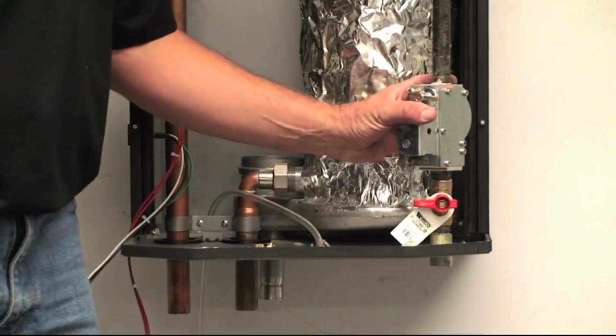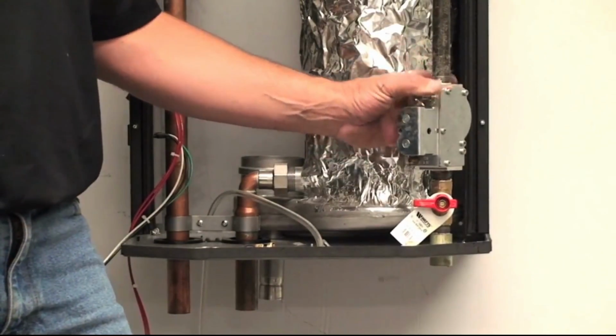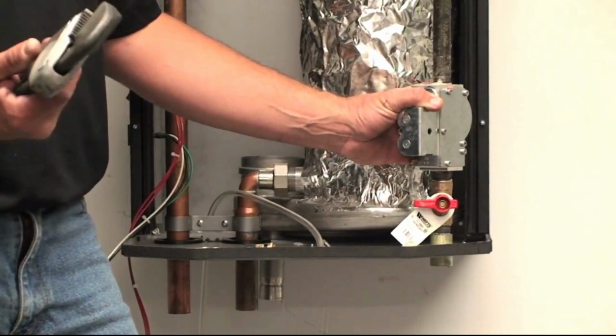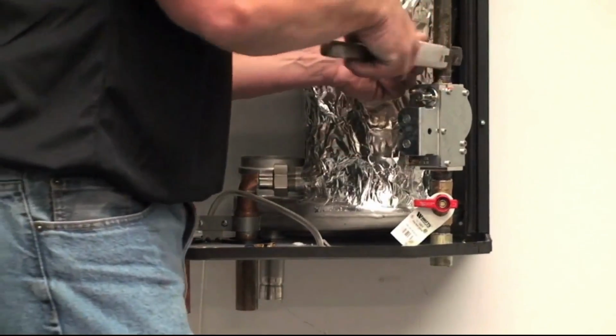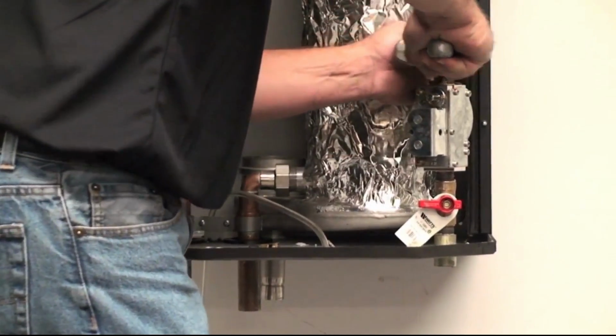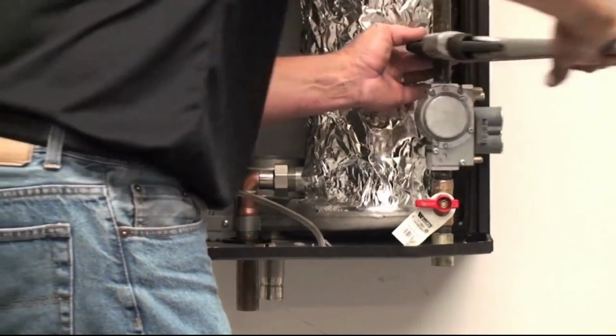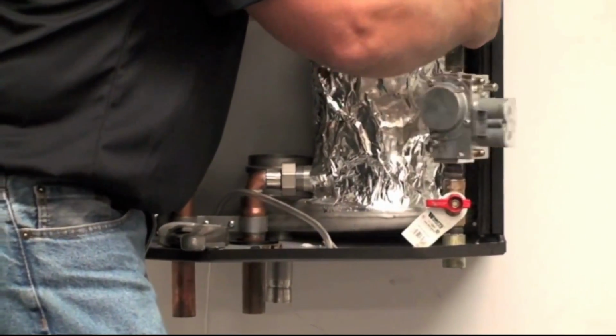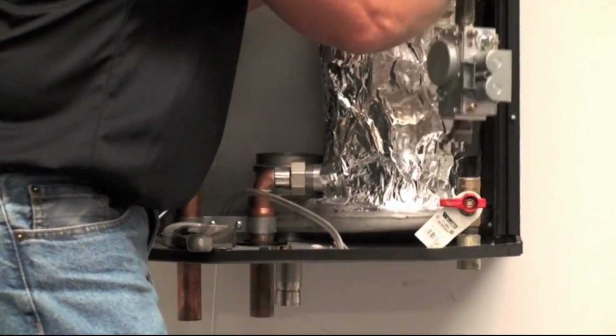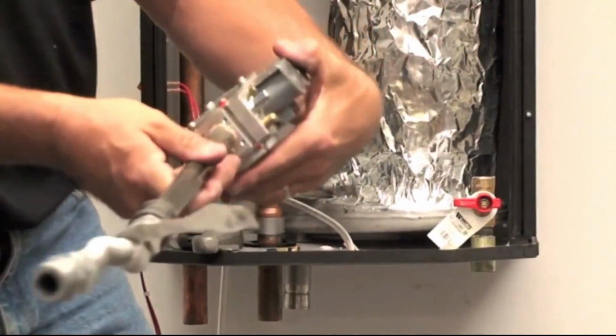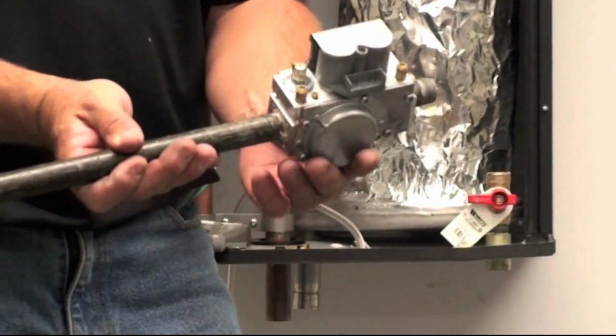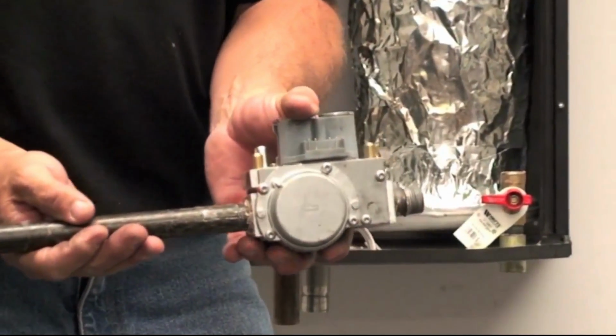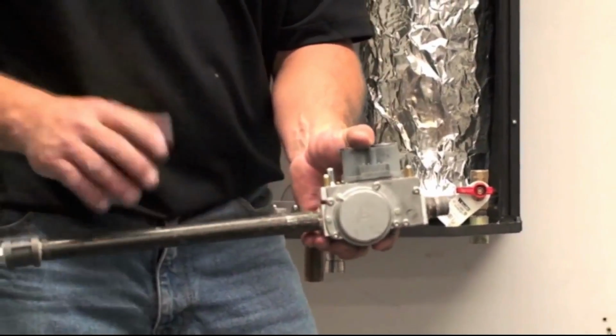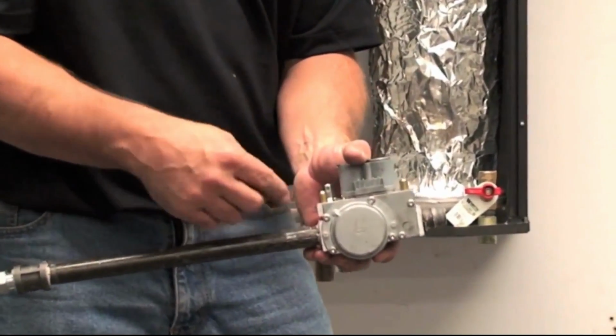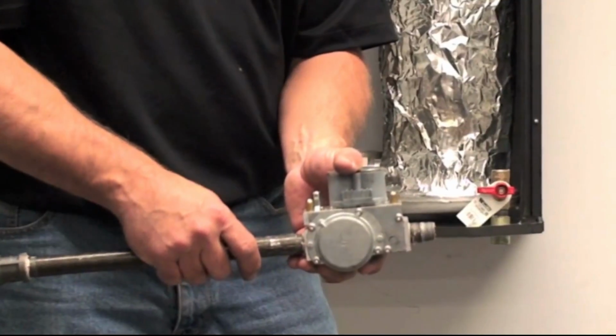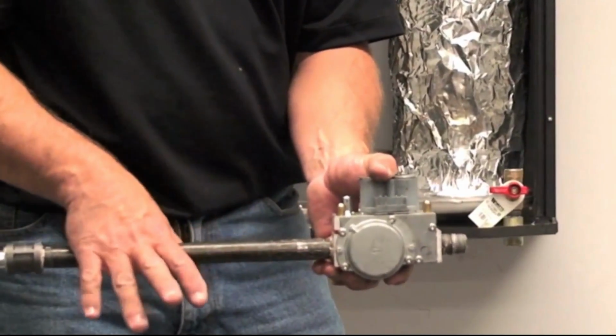The gas valve, to disconnect the gas valve if you ever need to replace it, you're going to simply take a pipe wrench and turn it. So you can take the gas valve off, and now this whole assembly's off. And what you can do is put it on a bench, clamp it properly to take any of the pipes off you need to. So when you reinstall them, you can dope them. It's better to do it that way. That way you'll have better seals.